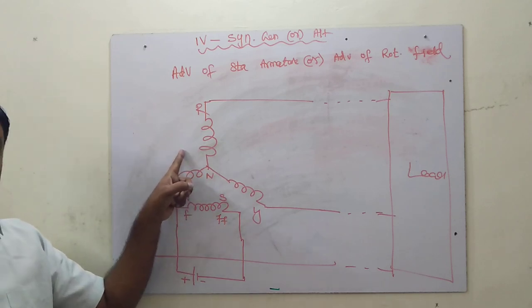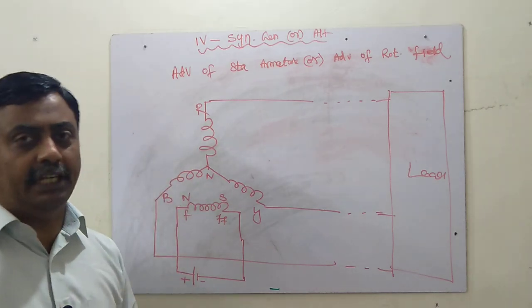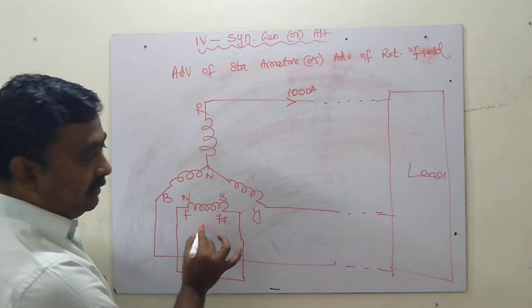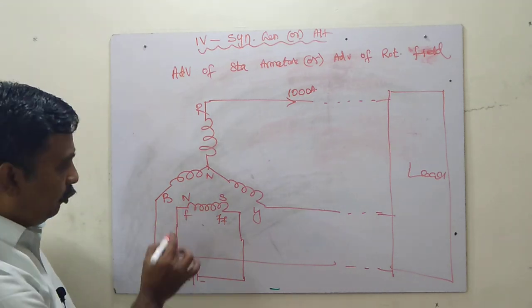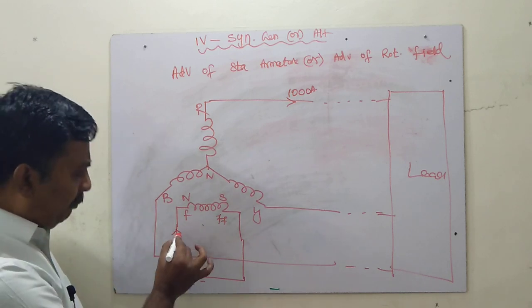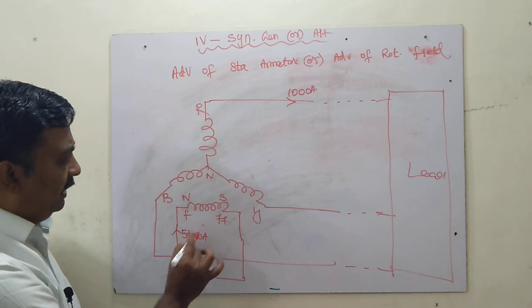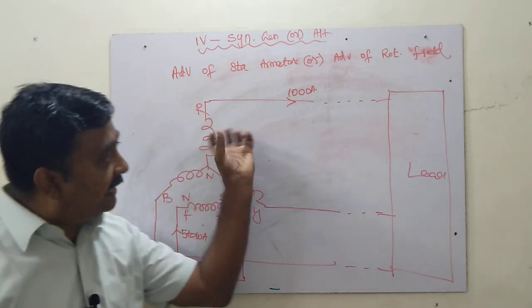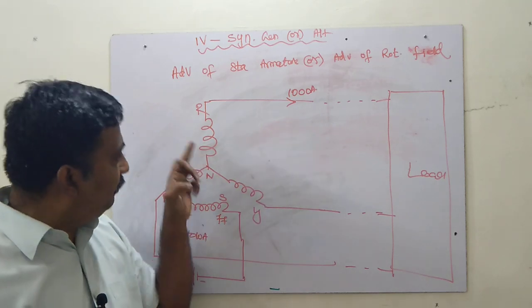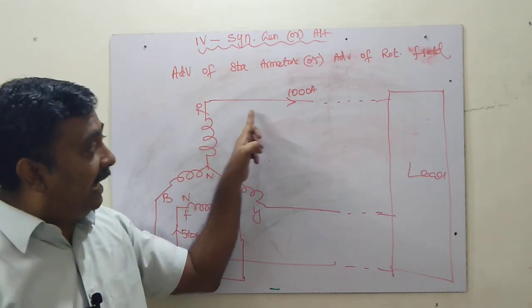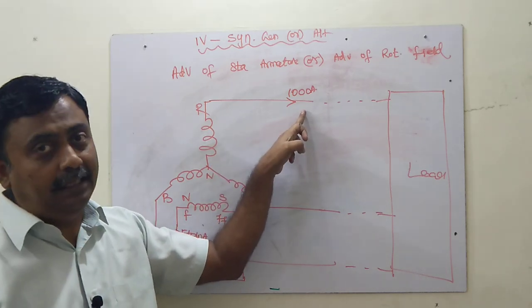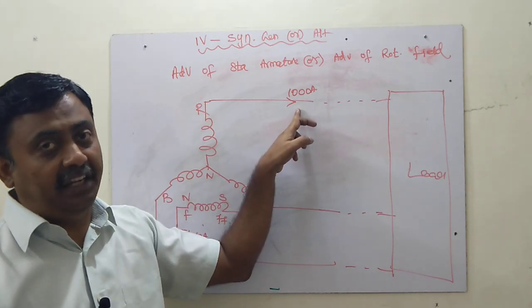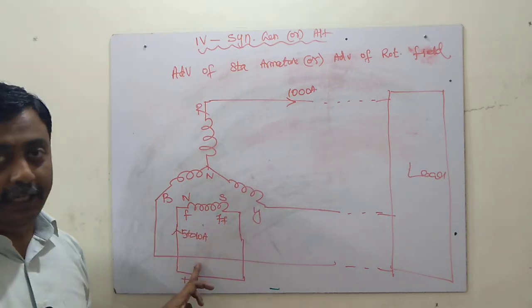What is the main advantage of having a stationary armature? The armature produces very high current — practically more than 1000 amps. The field, on the other hand, requires very little current — only about 5 to 10 amps maximum. If the armature were rotating, we would need slip rings and brushes to tap the energy, and at 1000 amps, the sparking at the brushes would be very high.